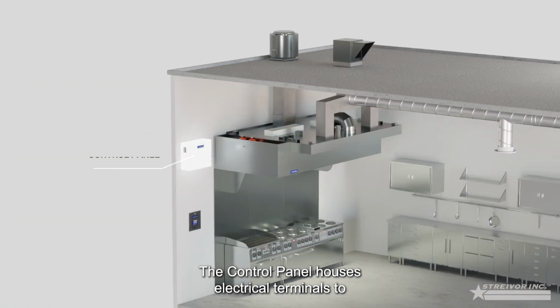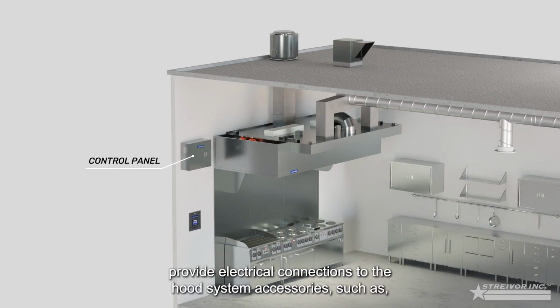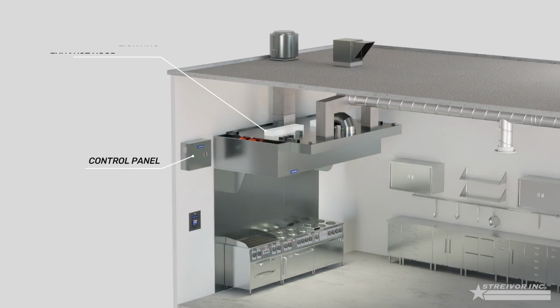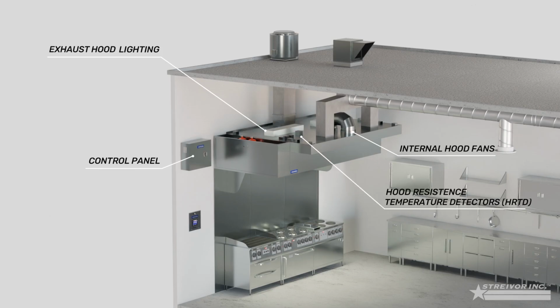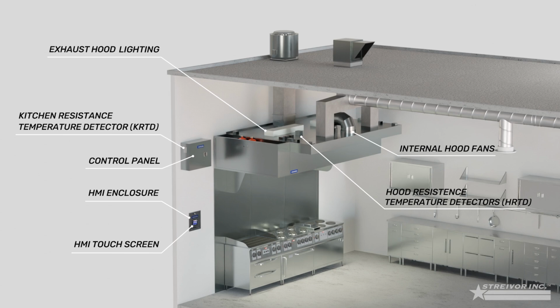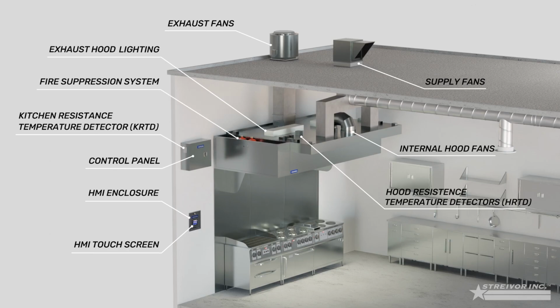The control panel houses electrical terminals to provide electrical connections to the hood system accessories, such as the exhaust hood's lighting, internal hood fans, if included, hood resistance temperature detectors, kitchen resistance temperature detector, human-machine interface enclosure and touch screen, exhaust and supply fans, and the hood's fire suppression system accessories.